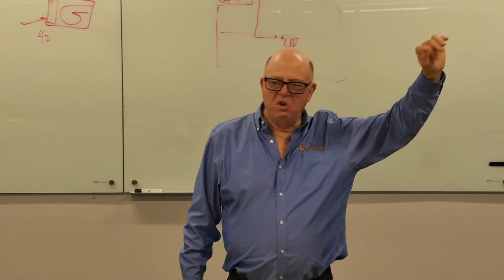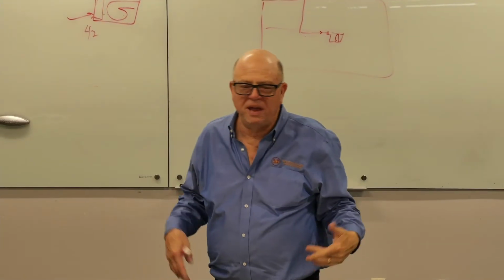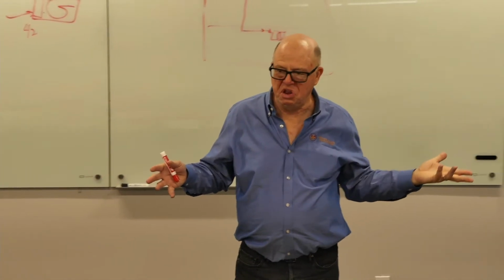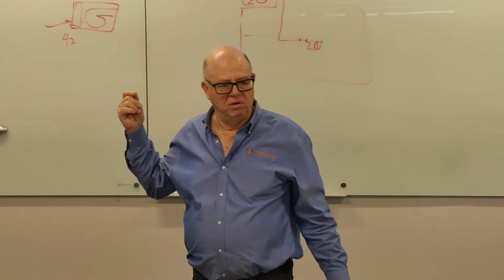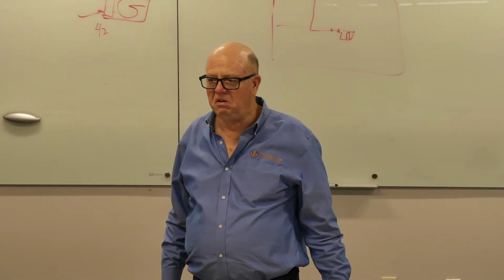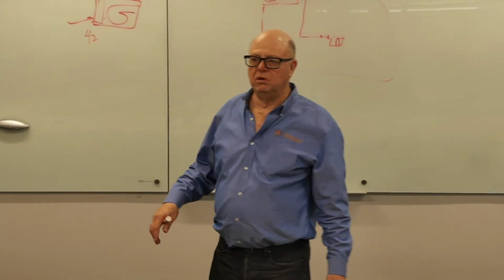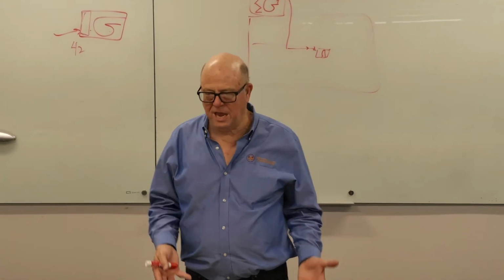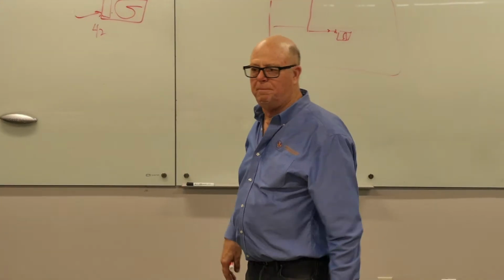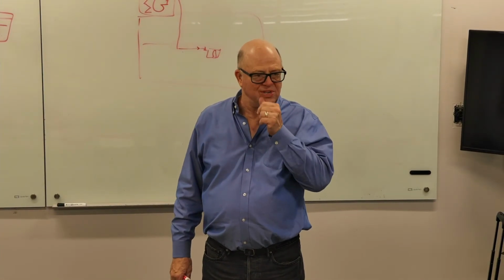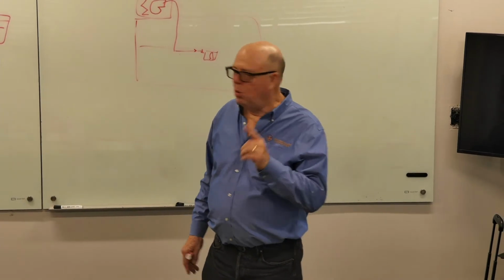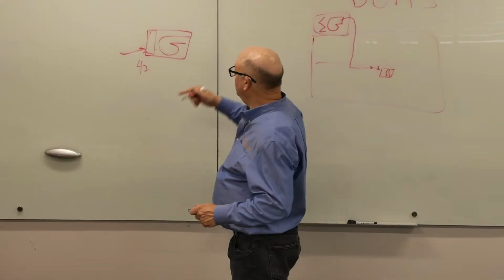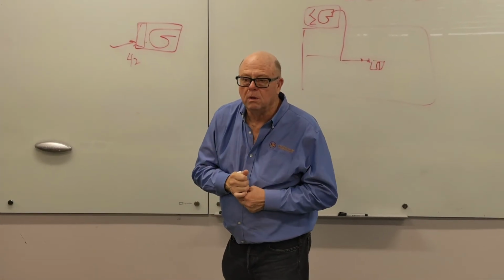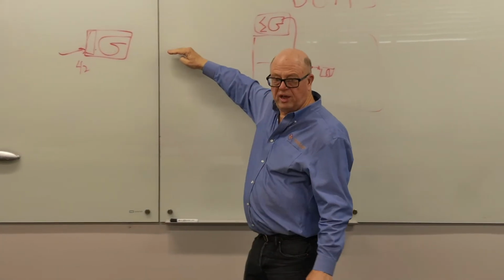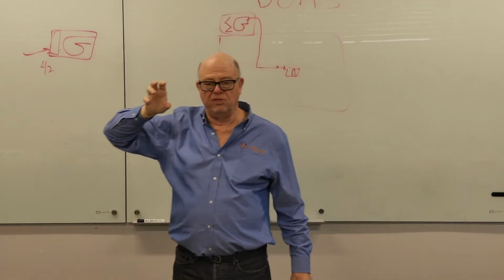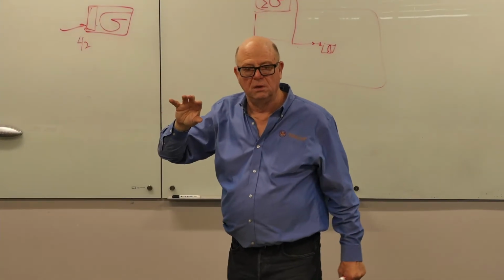If the standard residential size condensing unit split system had a SEER of 14, the VRF equivalent would be like 18, 17. No way. We just knew that all of those people from across the Pacific were lying about the ratings because the physics just wouldn't permit it. But there was something we didn't understand. What VRF does at low load, when you're down at, let's just say, 30% load, there will be some minimum CFM that will come across here, and it's probably somewhere in the 30 to 35% range of nominal. But what if you got even less load?